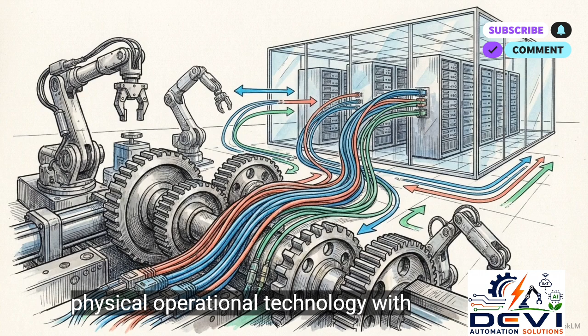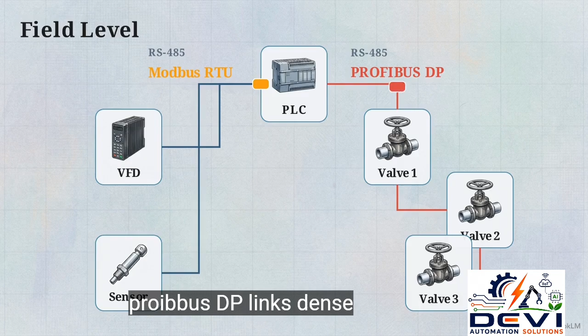Here at the bedrock of the automation hierarchy, a single sensor, VFD, and PLC connect via standard RS-232 or RS-485 serial links. Modbus RTU pushes data across these lines for direct device communication, while PROFIBUS DP links dense clusters of sensors and valves. With legacy analog instrumentation, the HART protocol layers digital diagnostic data directly on top of a standard 4 to 20 milliamp signal, extracting telemetry without disrupting baseline voltage.